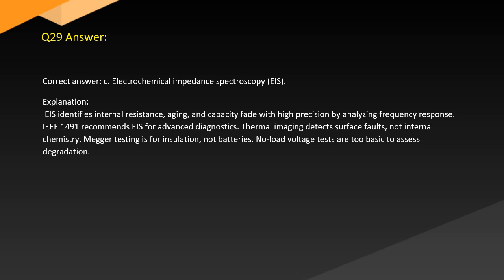Answer. Correct answer: C. Electrochemical impedance spectroscopy, EIS. Explanation. EIS identifies internal resistance, aging, and capacity fade with high precision by analyzing frequency response. IEEE 1491 recommends EIS for advanced diagnostics. Thermal imaging detects surface faults, not internal chemistry. Megger testing is for insulation, not batteries. No-load voltage tests are too basic to assess degradation.